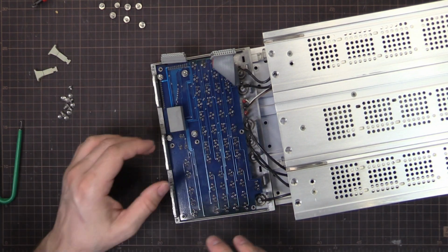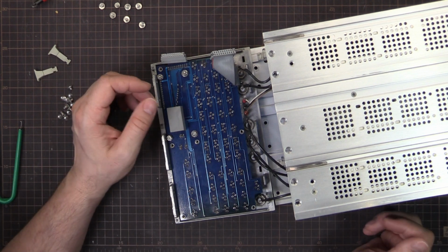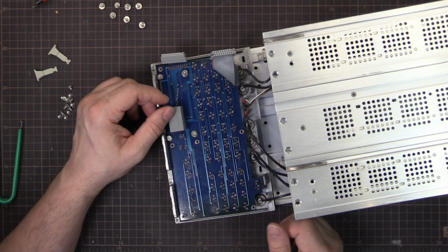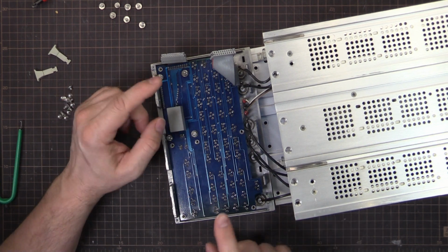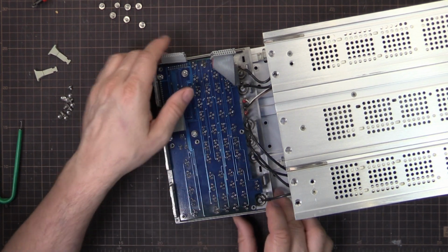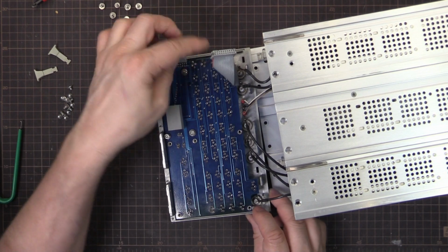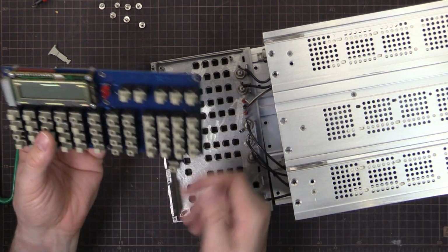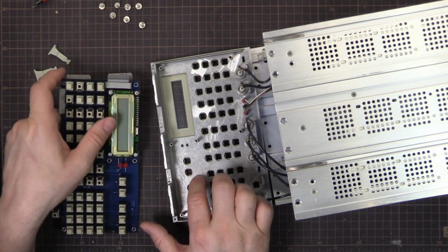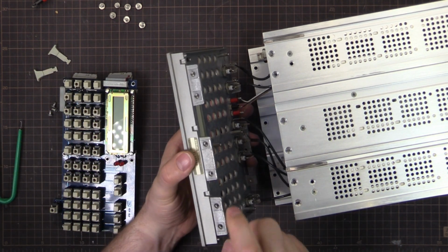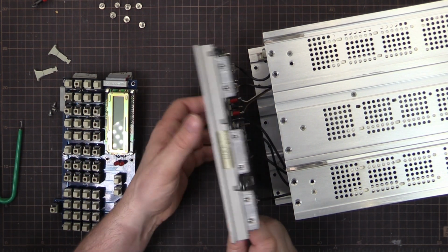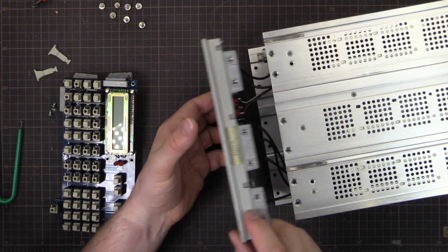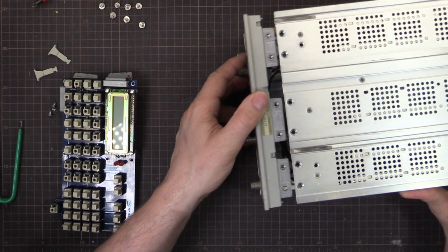But you don't really need to get into this part of the circuit at all. No, not for any calibration or anything. Only for what we're doing now, which, under normal operation, wouldn't be necessary. So that's fine. There's enough slack there to open this up. Then there's a bunch of screws on the back, and we can take the board out. Pretty easy. And that is cast aluminium, none of this plastic rubbish like on all the other TM500 modules. That is nice. So let's get that out of the way.